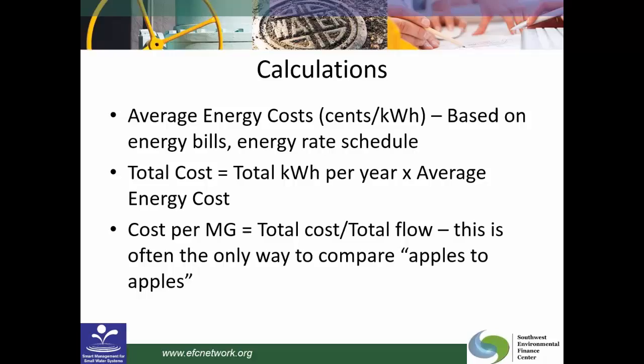Then you need to look at energy costs. So you're going to take your energy bills and your energy rate schedule. Your rate schedule might say that you're being charged 9 cents a kilowatt hour, but there are probably other fees and charges that go with that: demand charges, peak charges, seasonal charges, you name it. There are different charges in all kinds of electric bills. So I think it's better to use an average energy cost than to use your rate schedule. If the rate schedule says it's 9 cents a kilowatt hour, chances are when you add in all the other charges and fees, it might be closer to 12 cents a kilowatt hour.